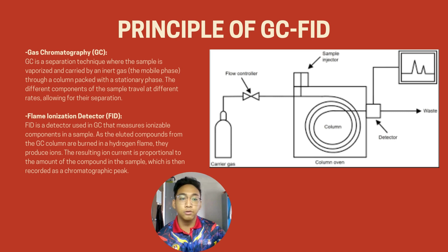as a chromatographic peak. The flame ionization detector operates by vaporizing the sample in a hydrogen or air flame, breaking down organic molecules into ions through combustion and collecting these ions on a bias electrode to measure as a current. This detector is cost-effective, requires minimal maintenance, and can withstand harsh laboratory conditions, making it suitable for gas chromatography analysis.